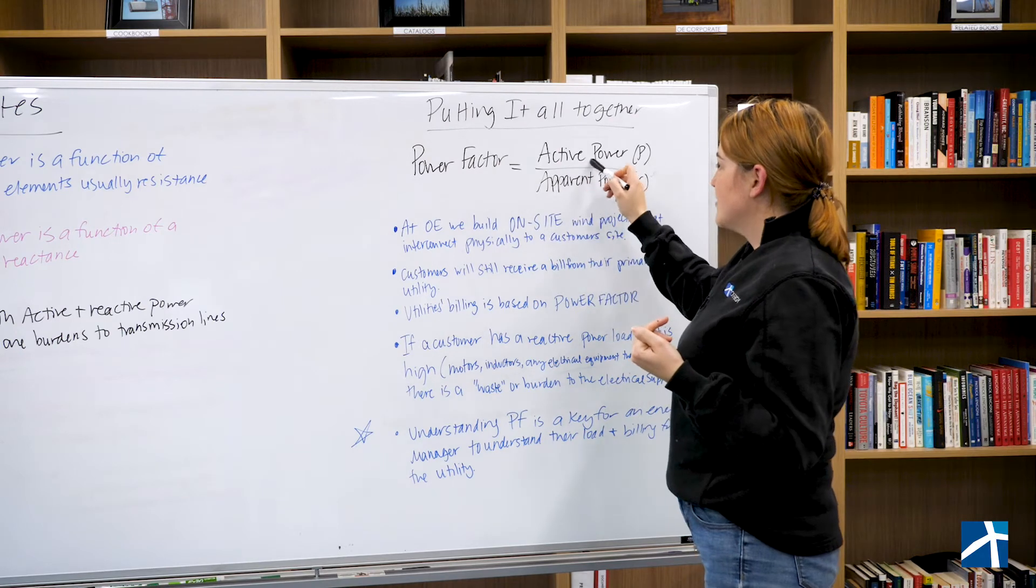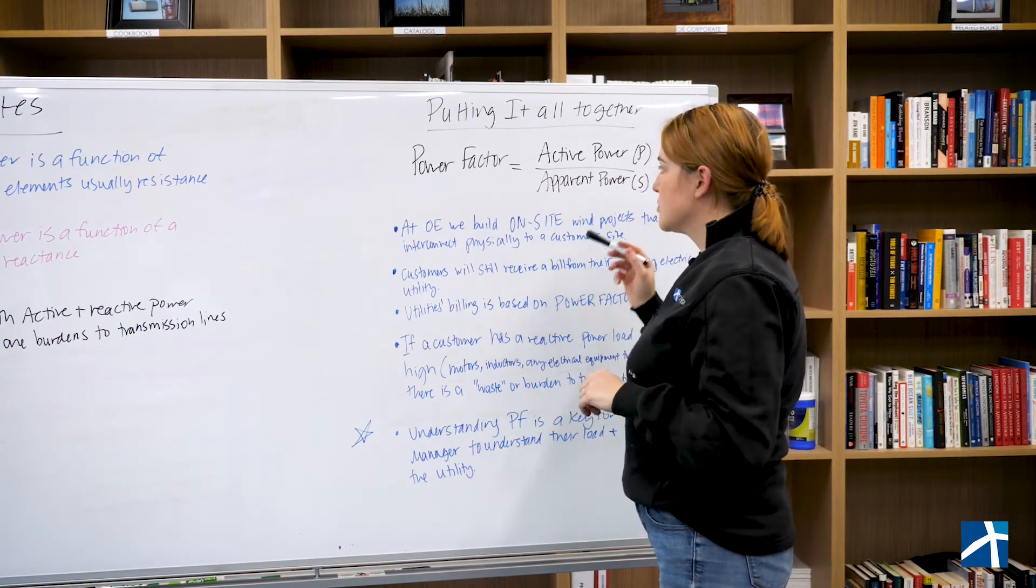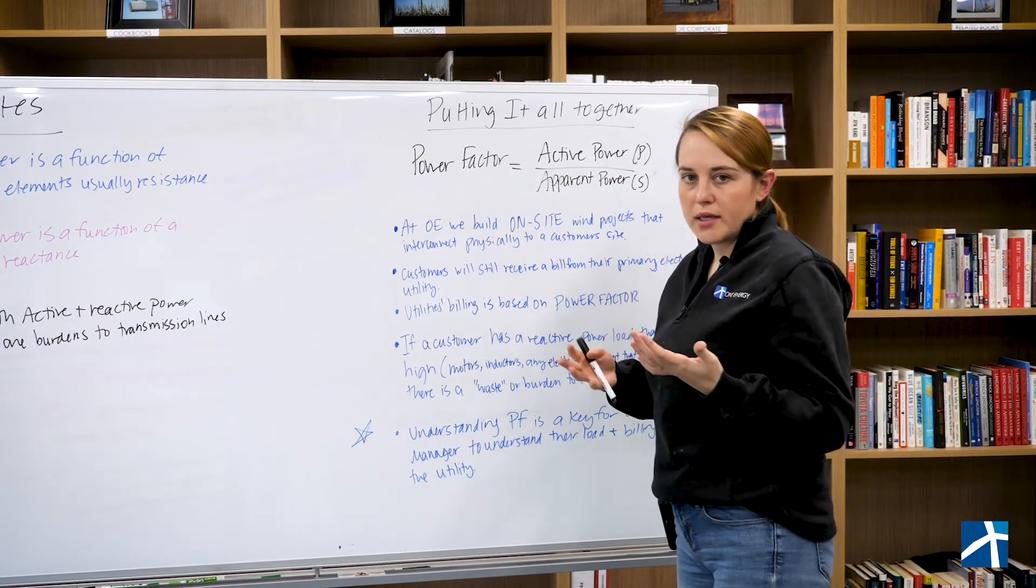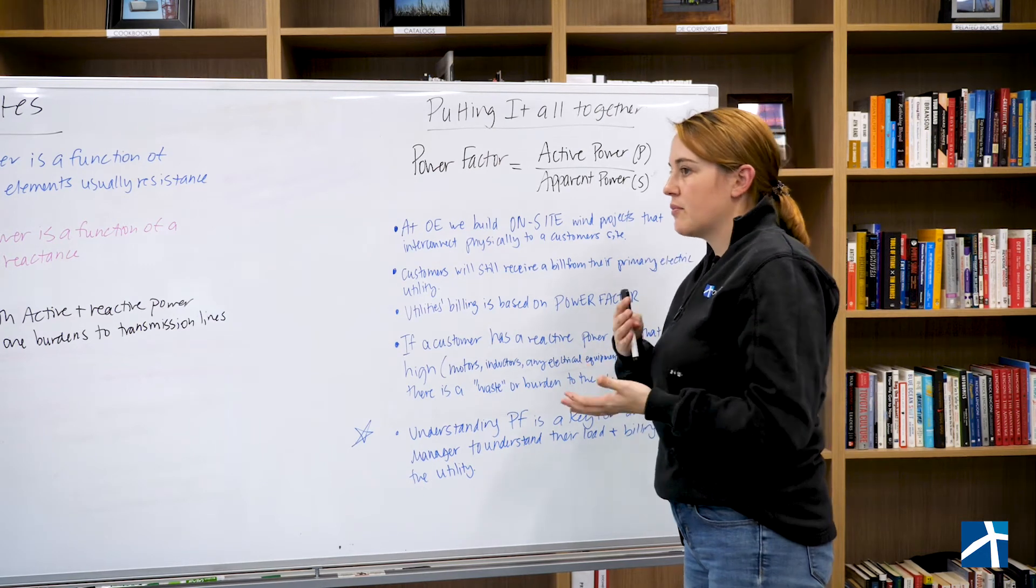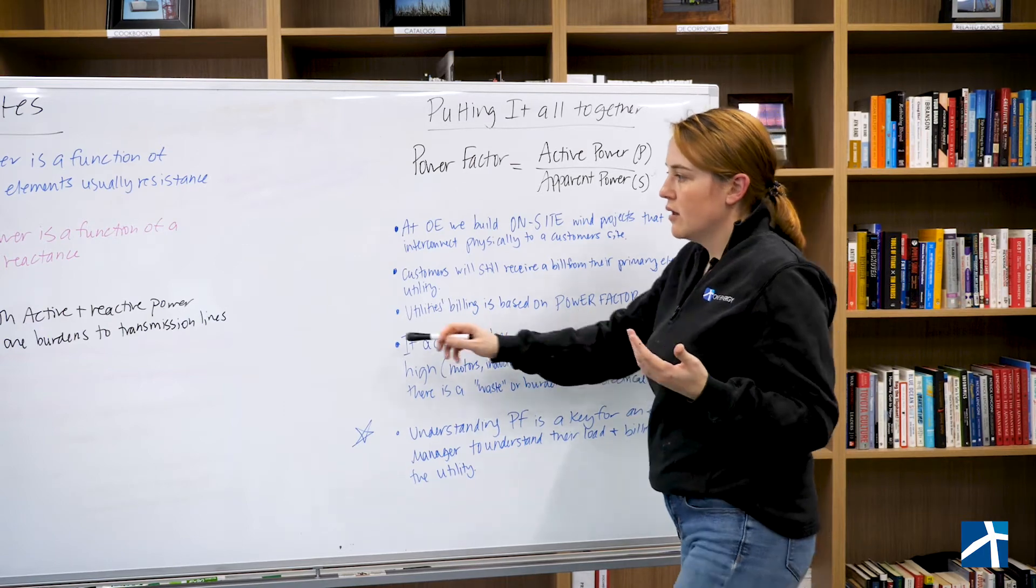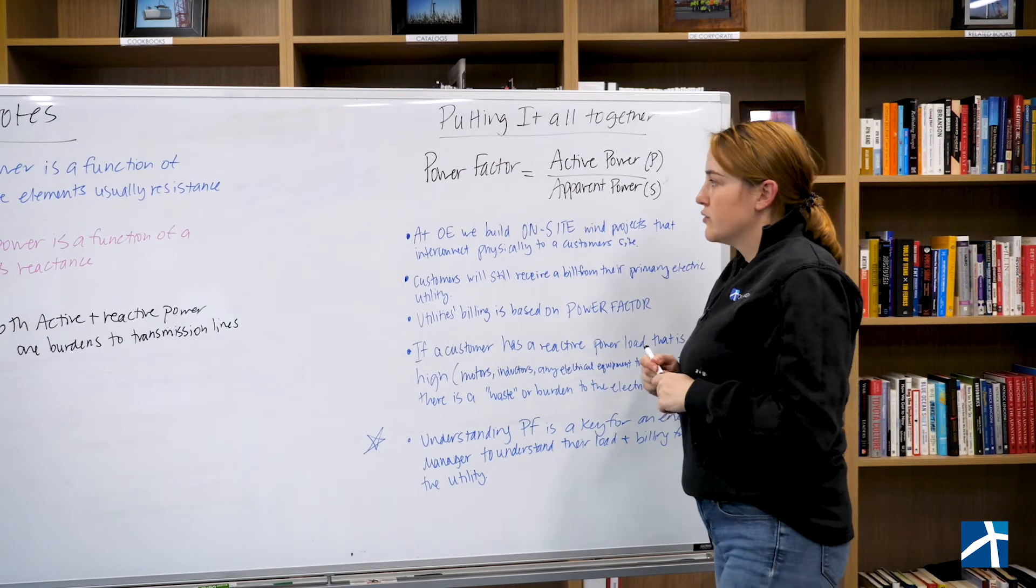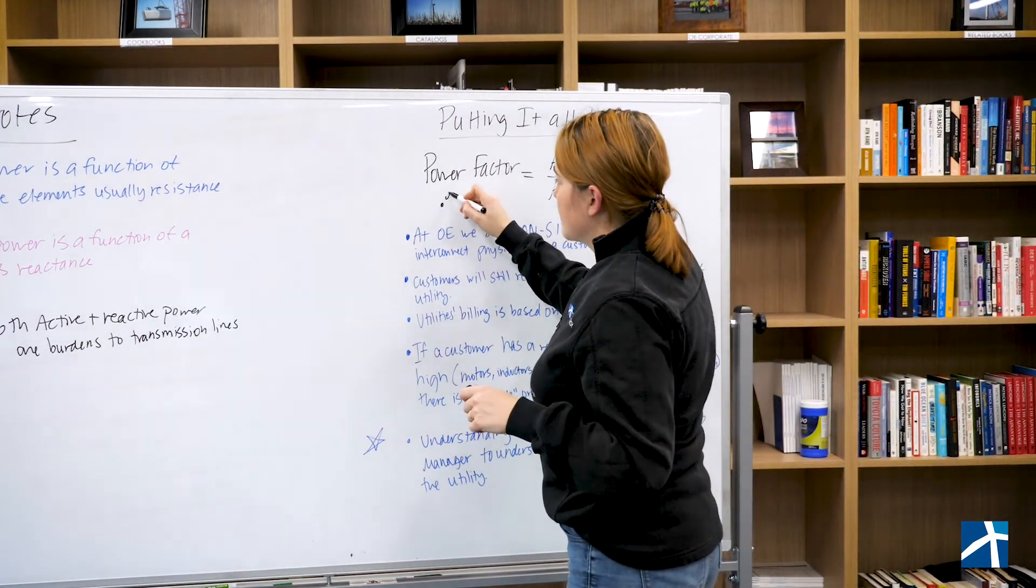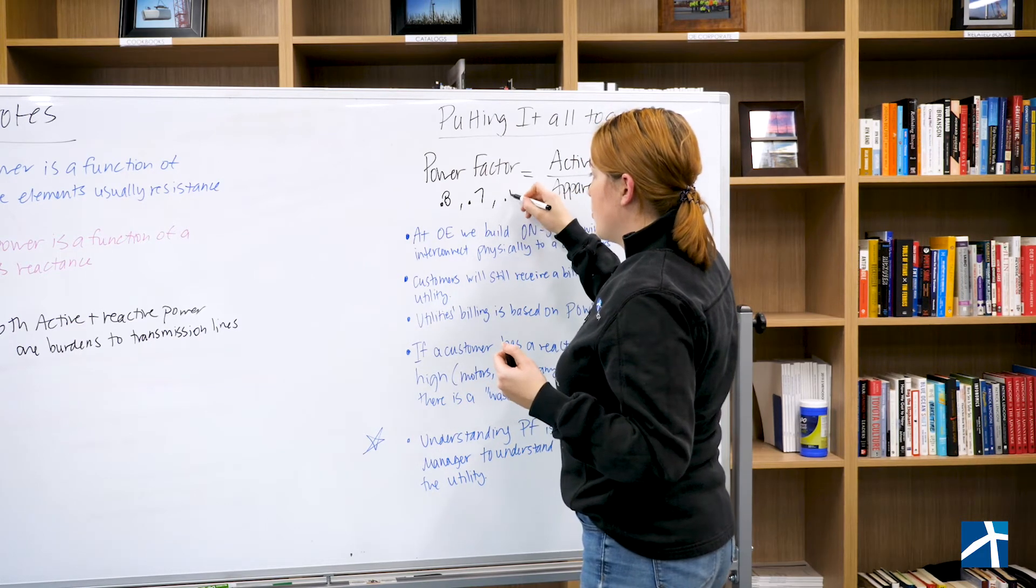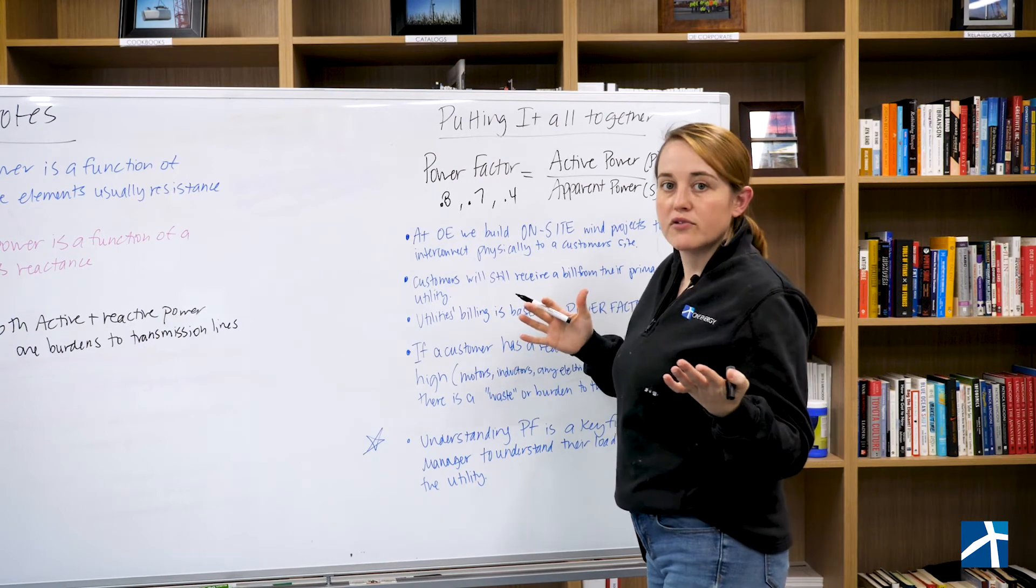The ratio of active power to apparent power is called your power factor. So this matters a lot when you're talking about utility billing. And so a utility is going to look at, let's say a plant's overall power factor, and they're going to say, okay, both active power and reactive power are burdens to the transmission line. So they're going to bill differently as if this were 0.8, 0.7. They're going to bill very differently if it's 0.4. It all depends on what's in the fine print of your utility bills.